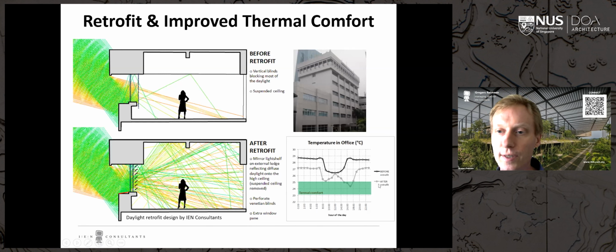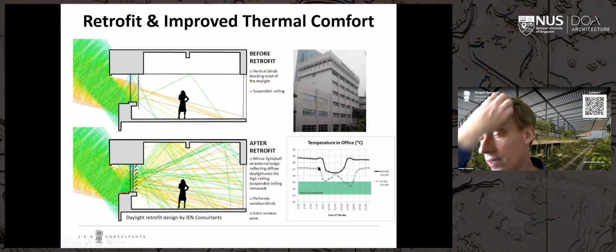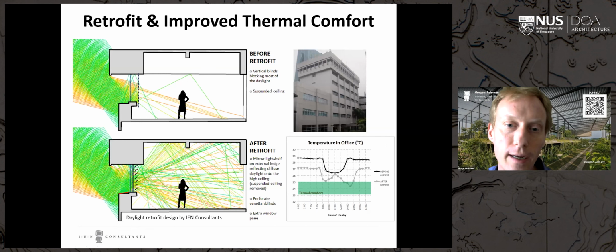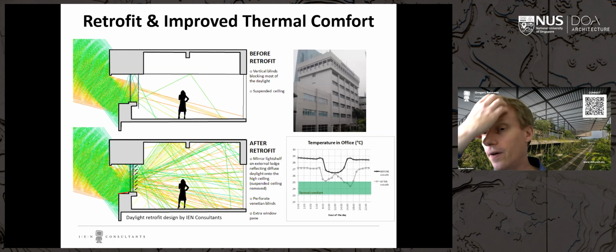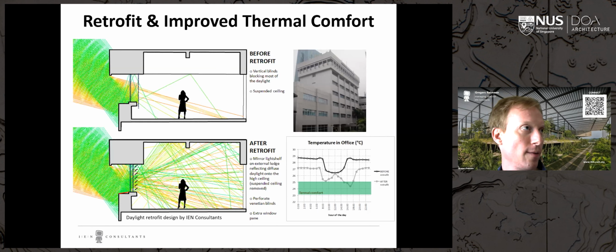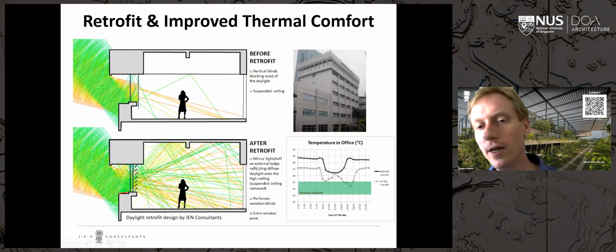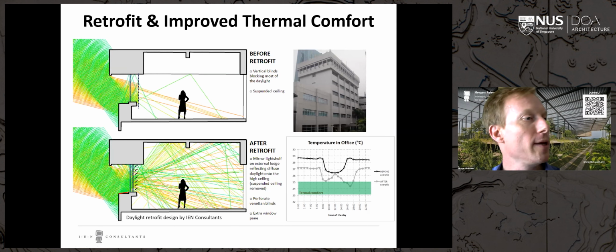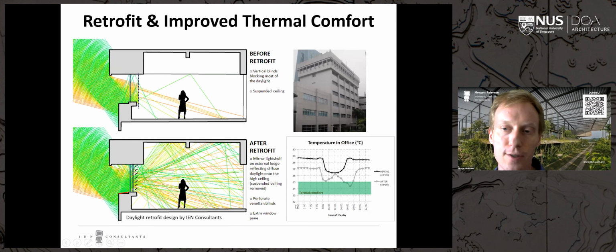After the retrofit, we also changed the aircon system. We put our own VRF on the roof and made this system have demand ventilation control, measuring CO2 - so if there were fewer people in the office, it would reduce the amount of fresh air pumped into the space. This was quite an efficient cooling system compared to the old one, and we could switch it on and off ourselves.